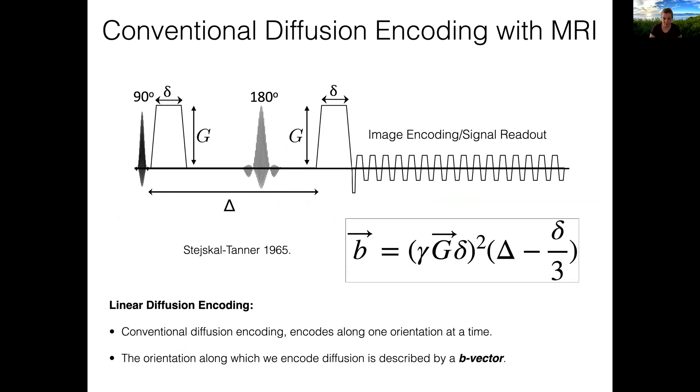It is also amazing to consider that the way we encode diffusion hasn't really changed in more than half a century. The majority of diffusion MRI scans today still use the same pulsed field gradient scheme presented by Stejskal and Tanner in 1965. We will refer to this conventional type of encoding as linear encoding because in contrast to the encodings we will discuss in a moment, it encodes along one orientation at a time and that orientation is captured by a b-vector.